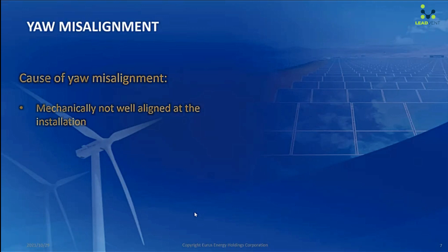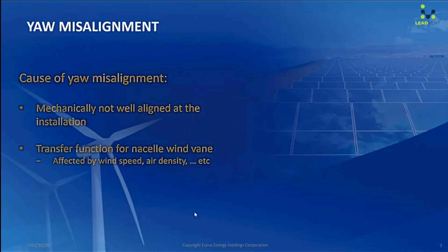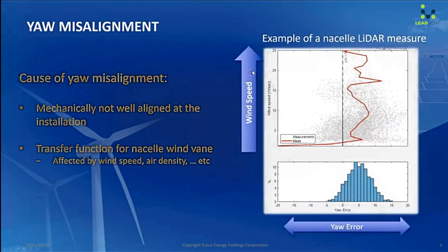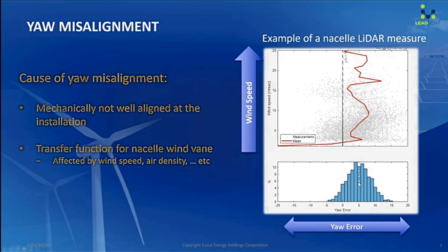The causes of misalignment can be mechanical misalignment installed at the beginning. Another one is the transfer function of the wind vane, which is complicated because it can be affected by wind speed and air density. For example, this is a measurement from a nacelle lidar. The bottom graph shows the distribution of wind direction relative to the nacelle — in this case the misalignment is about five degrees. Looking at the top figure showing wind speed, the misalignment angle is depending on the wind speed in this case.